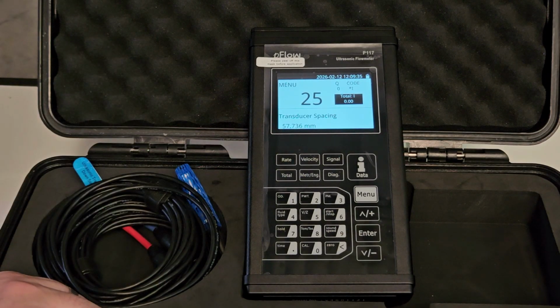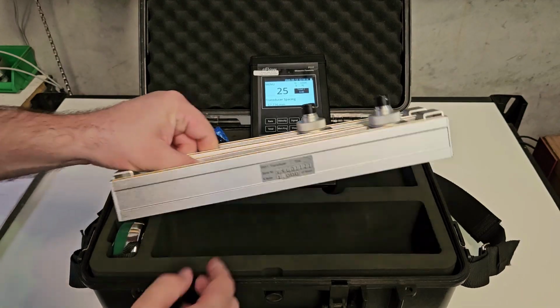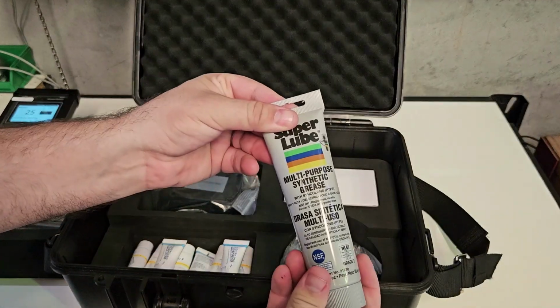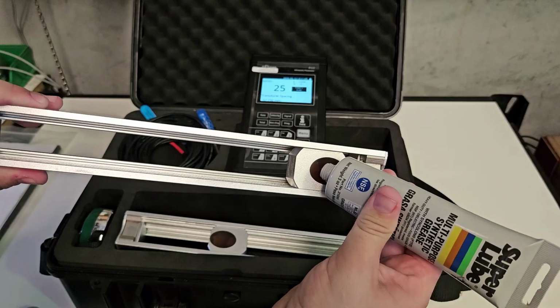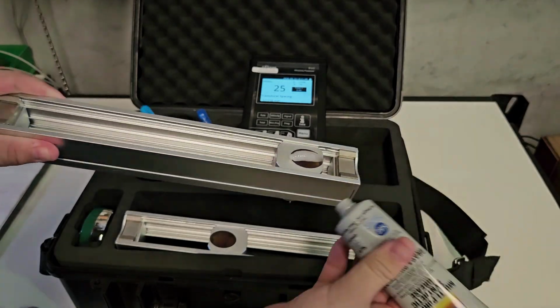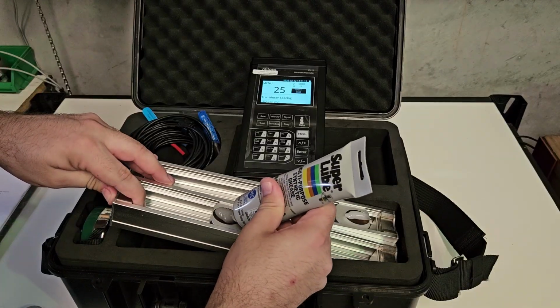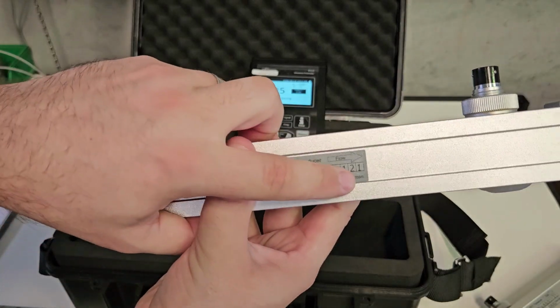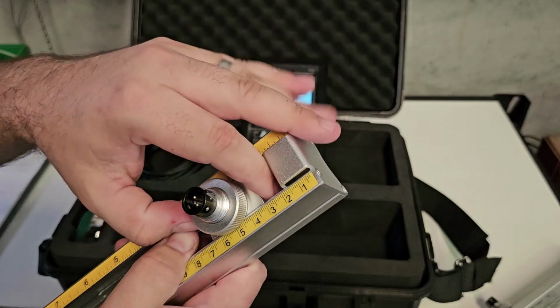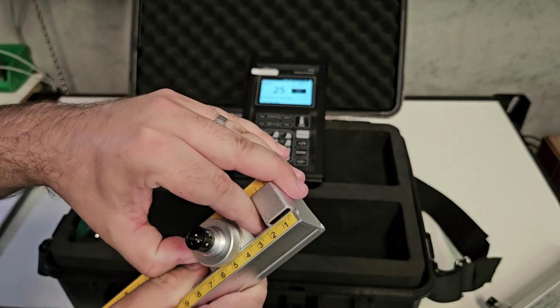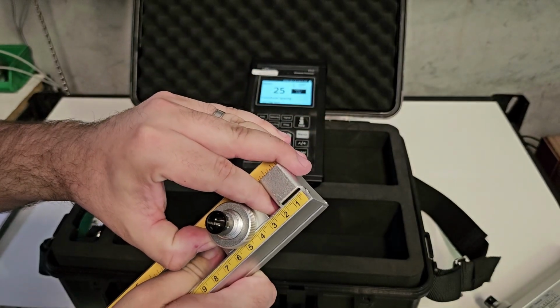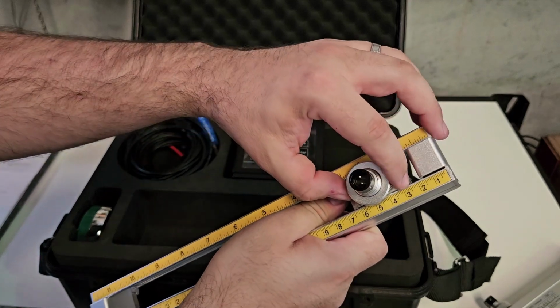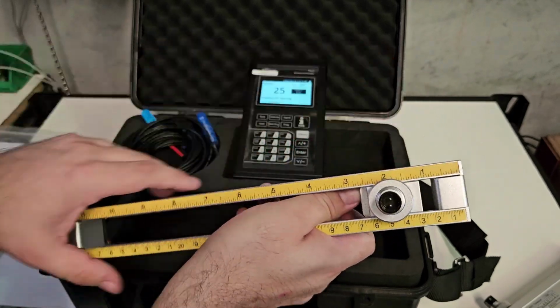Now we can prepare the sensors. Pull them out and take some couplant. Apply a blob on the surface of both sensors. Use enough to cover the brown oval once it's squished onto the pipe. Next take the upstream sensor, checking the label and noting the flow direction. Begin spacing the sensor in the frame, remembering the total space needed between both sensors. So on this one, I will space it around 2.77 centimeters from the end.